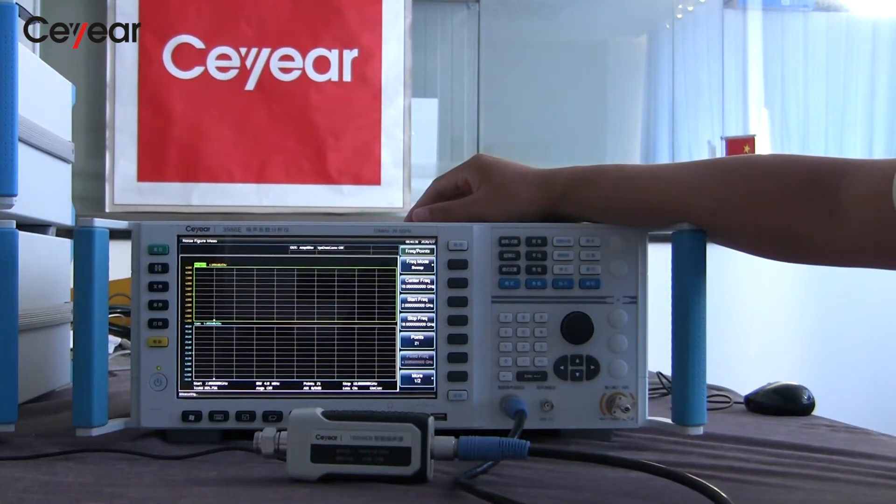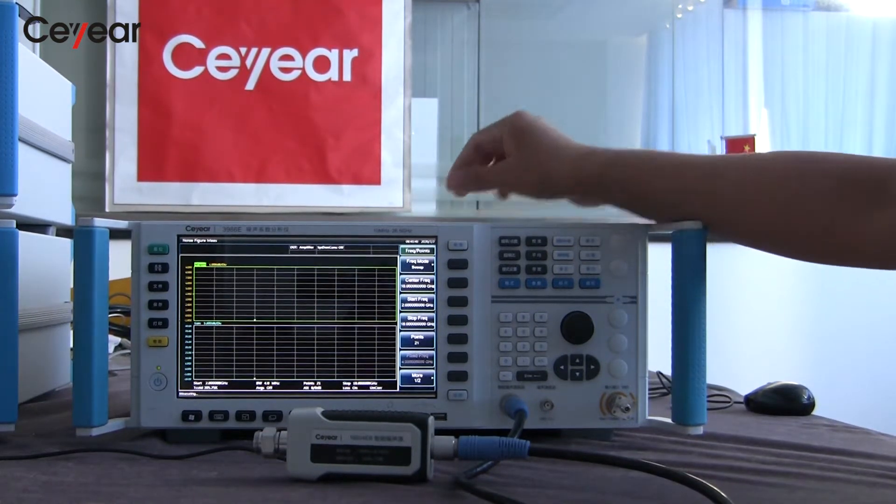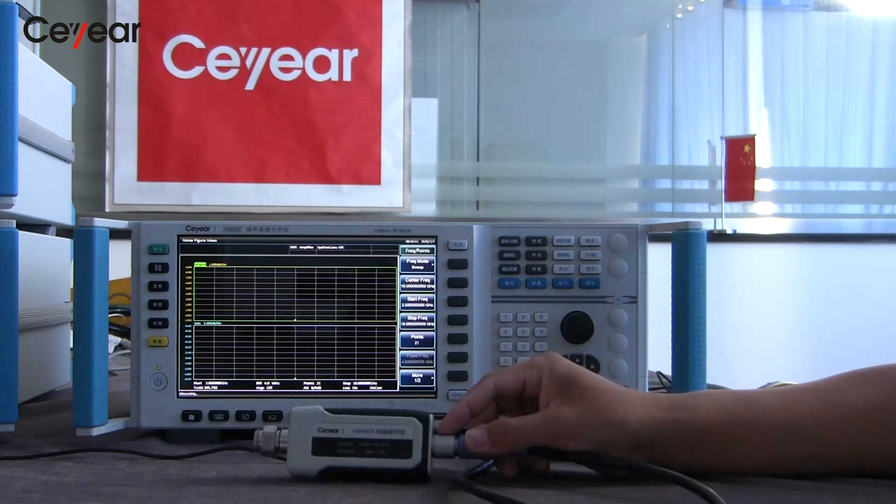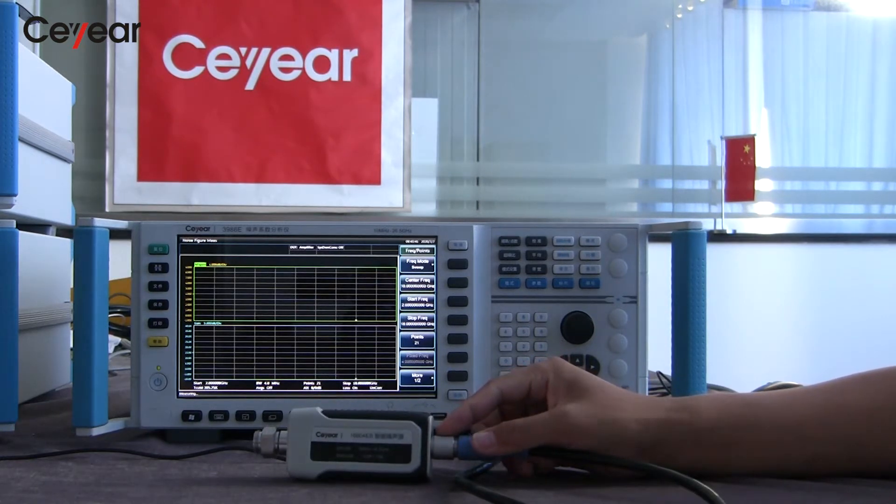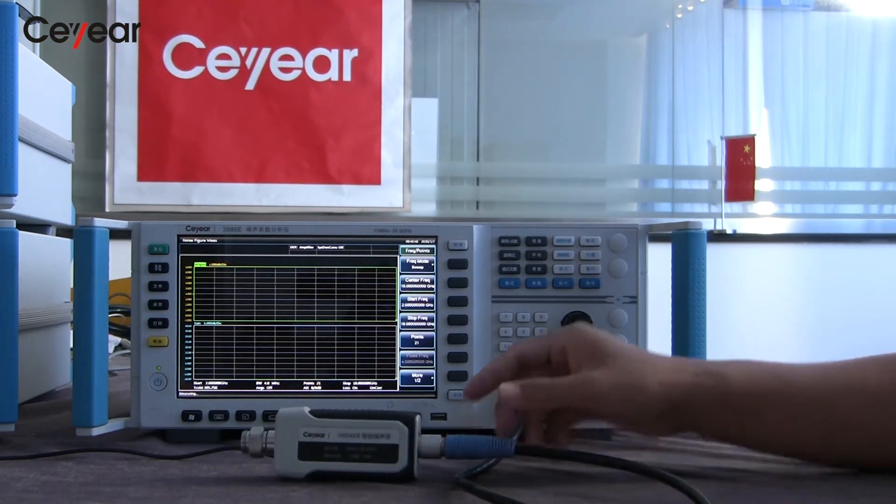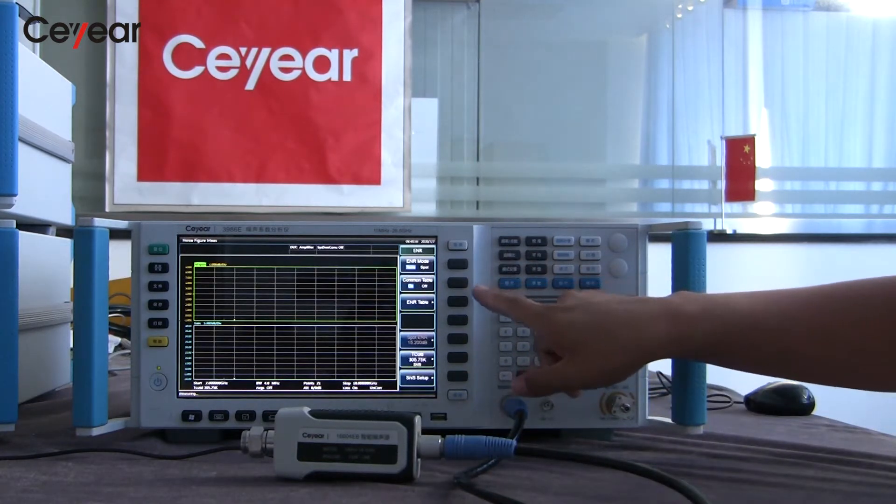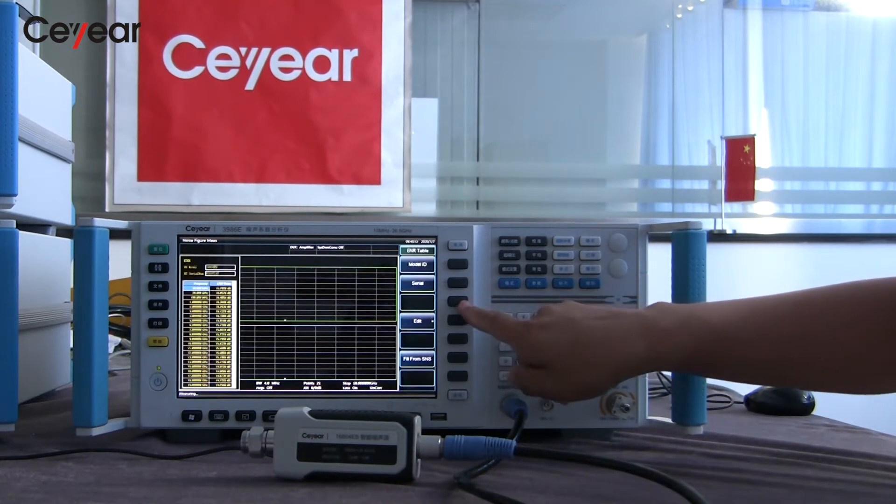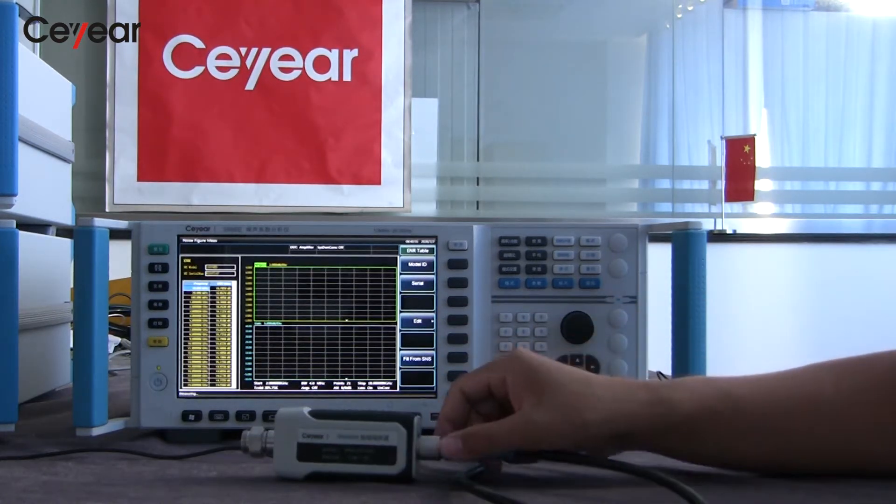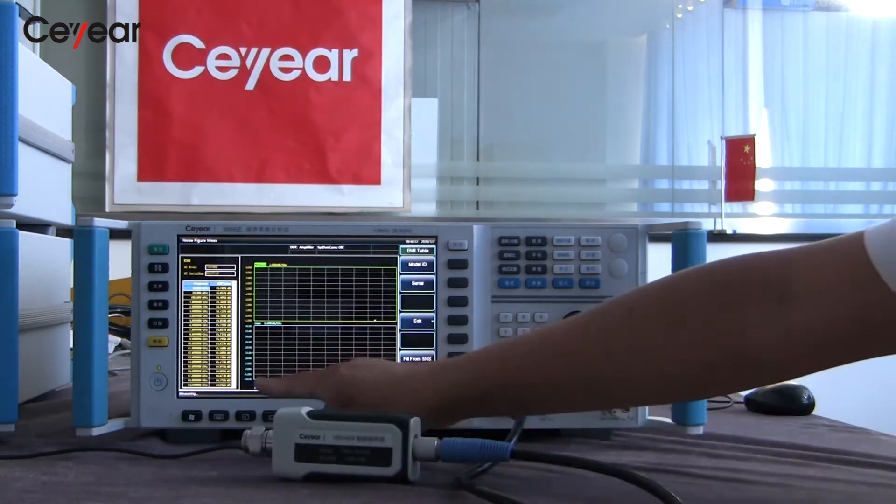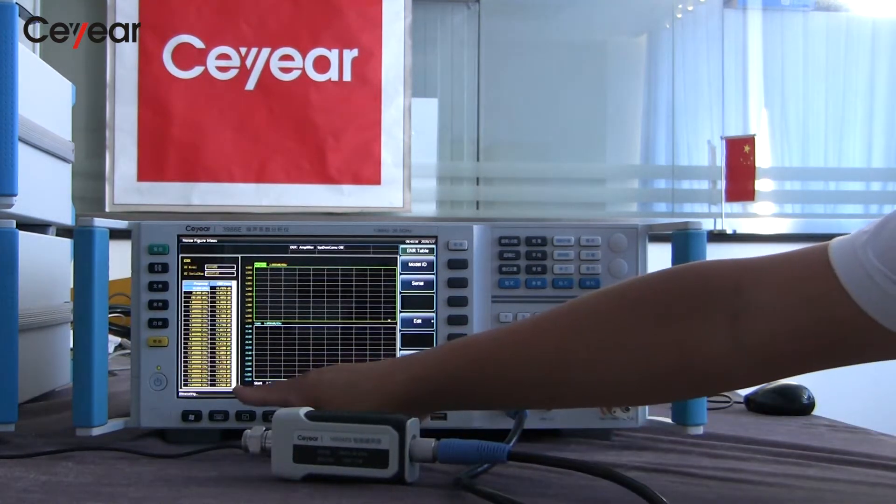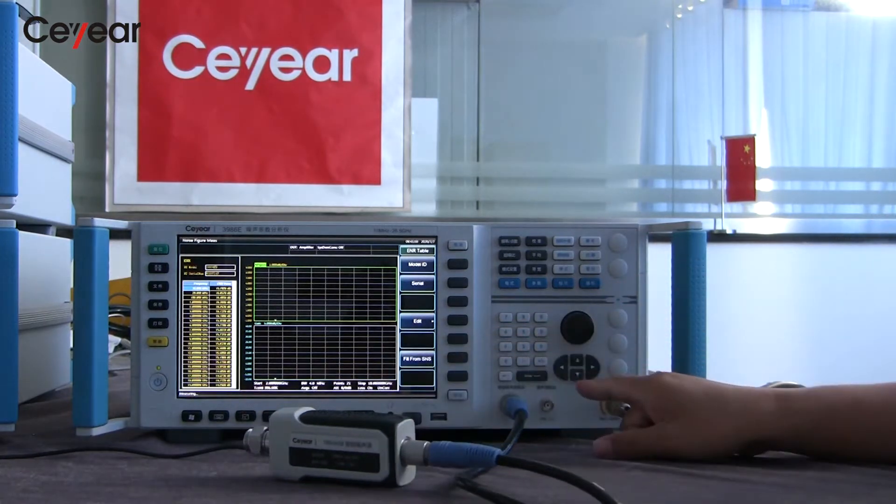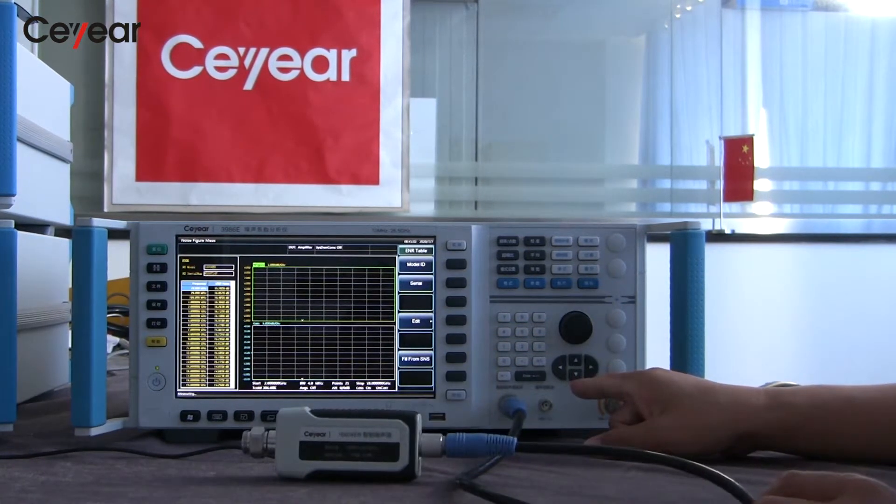Ceyear noise figure analyzer can support traditional BNC and smart noise source. This is our high-performance noise figure analyzer and the smart noise source. When using smart noise source, the ENR data can be automatically downloaded into the instrument. You can use the menu to check the ENR table if you want.